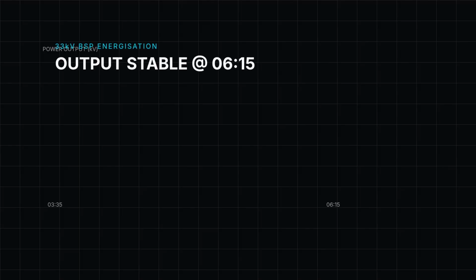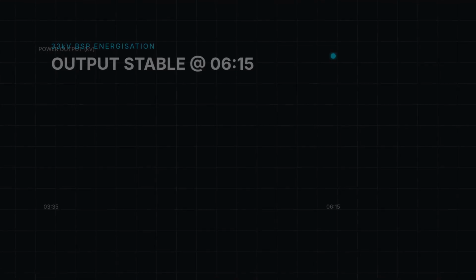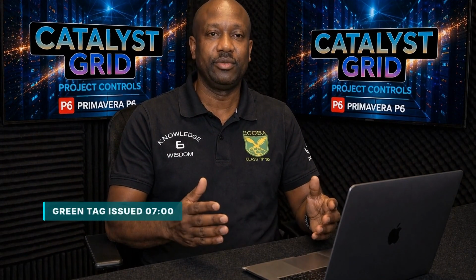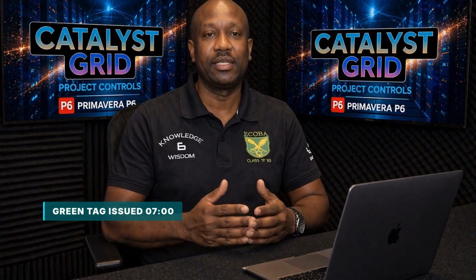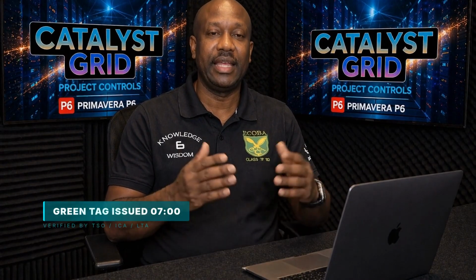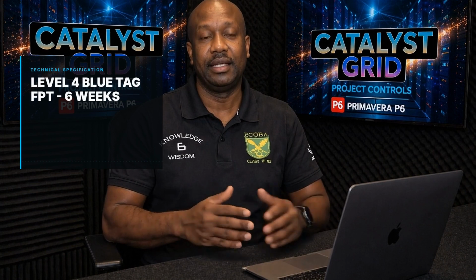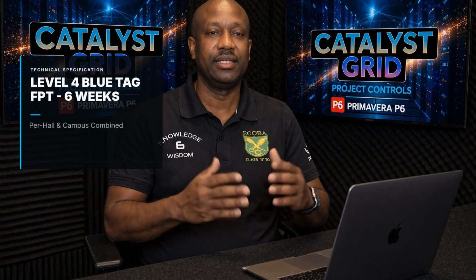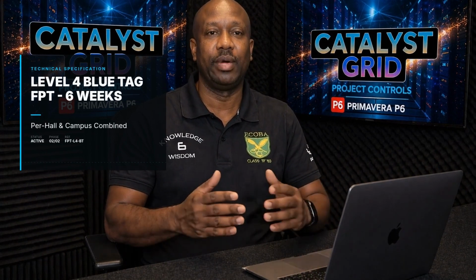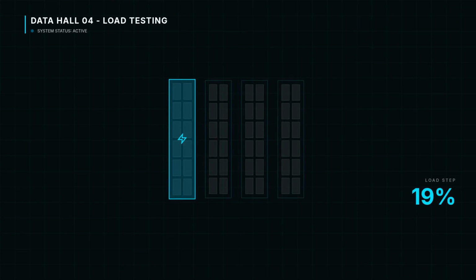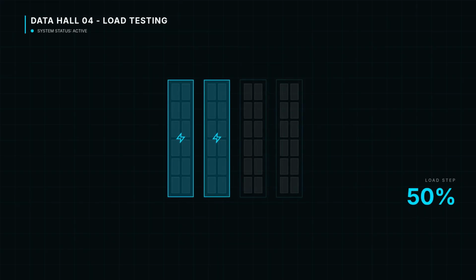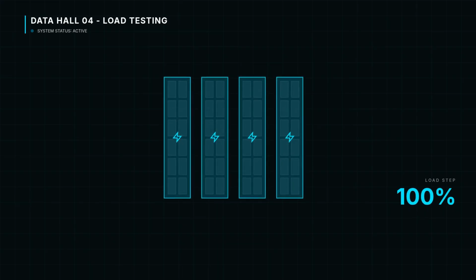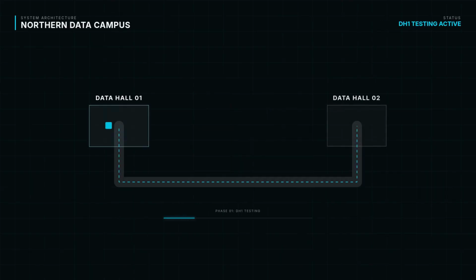The BSP energization took 2 hours and 40 minutes. By 6:15, the 33 kilovolt output to the on-site compound was confirmed stable. The green tag was applied to the 132 kilovolt switchgear at 7 a.m., witnessed by the TSO, the ICA lead, and the LTA. Level 4, blue tag. Functional performance testing is conducted in 2 stages, per hall testing followed by campus-wide combined testing. Each hall is tested independently at 4 load steps, verifying the cooling system, power distribution, and monitoring systems at every stage. Data Hall 1 testing runs first for 4 weeks.